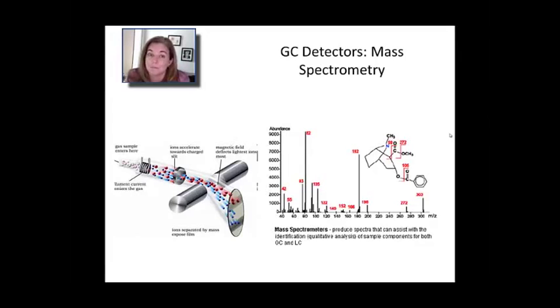You basically take the column, comes off the column, and you run it through a mass spec where you use magnetic fields to deflect the trajectory of ions. And through that, measure the ion current in the detector of the mass spec. They're substantially more expensive devices, much more complicated devices to run. You have to be very careful not to contaminate the inside of a GCMS. Because remember, it's pumped down. It's got a lot of the complexities that we saw with the ICPMS for atomic analysis. For example, as shown in this image, if you get a peak in a chromatogram, you have no idea what the chemical identity is. You can run a mass spec. You can take just that window, just that one, and figure out a lot about what you've got in the sample. So it's a really powerful tool, and one that we'll talk a lot more about.